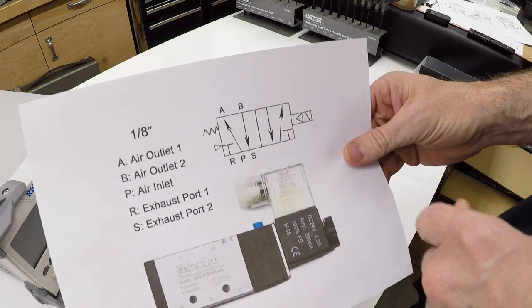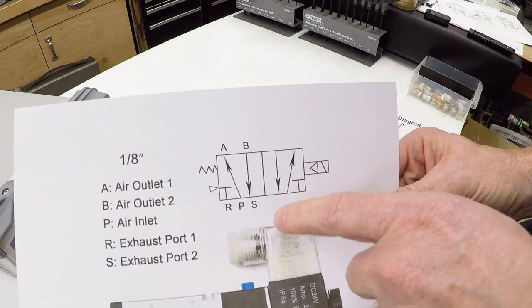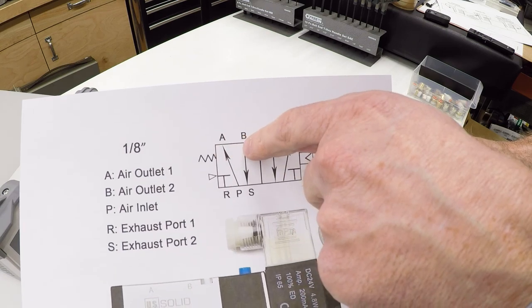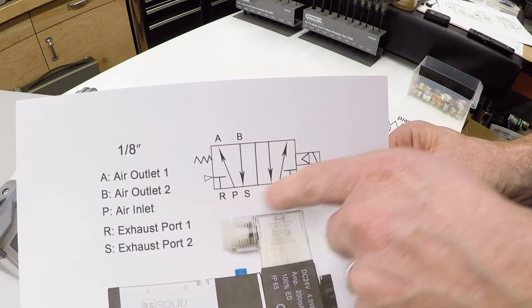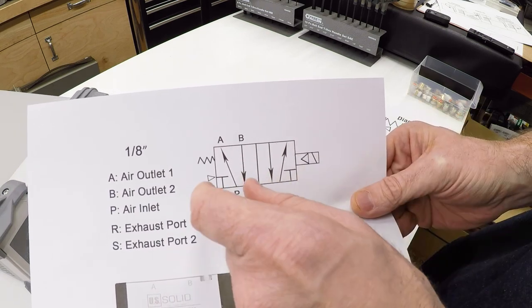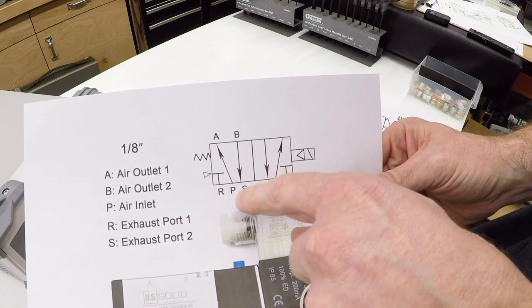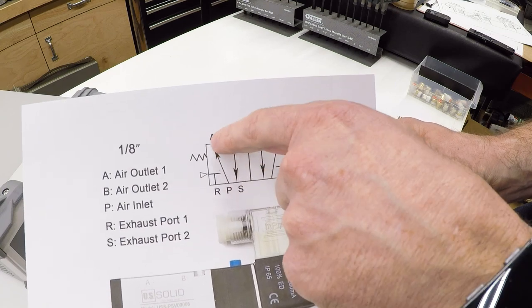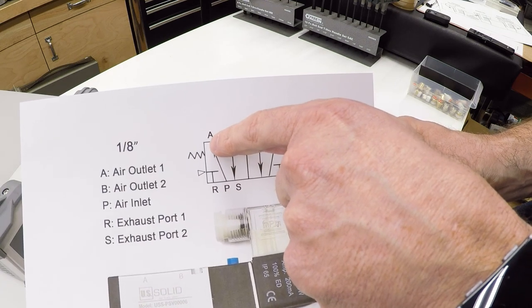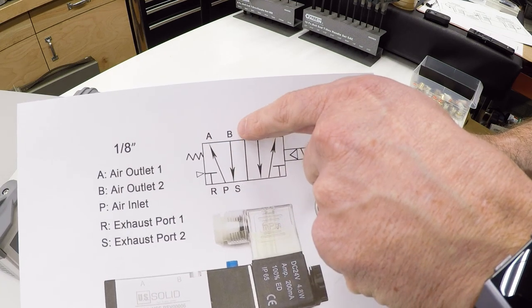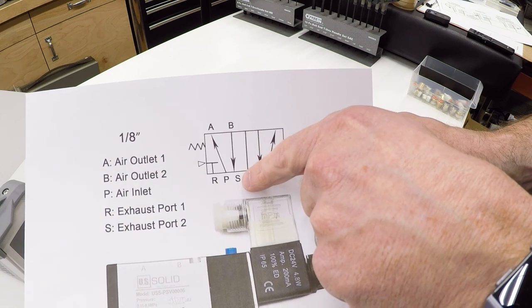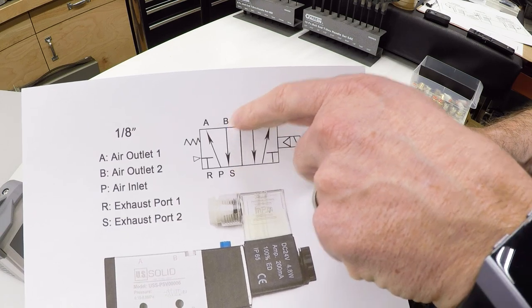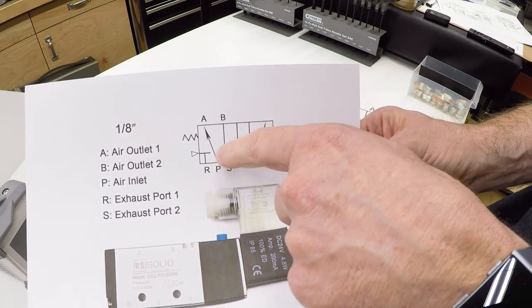The diagram for this valve looks like this. We've got the five ports, the P for the pressure port, A and B for the two sides of the cylinder, and R and S, two exhaust ports. It has two states. Normally, the spring returns it to this state, where the pressure is connected to one end of the cylinder, either extending or retracting it. And the other end of the cylinder is exhausted to atmosphere so that it can move, because the air has to be released from the other side of the cylinder in order for it to be able to move.